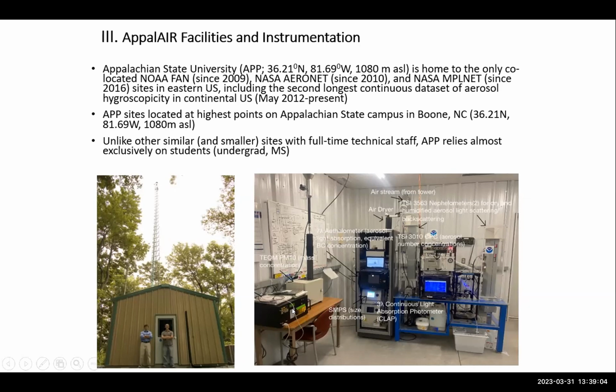This is what's called a tapered element oscillating microbalance, which measures PM10 mass concentrations. This instrument here is called a CLAP. It measures aerosol light absorption. And you have two nephelometers here and here. The first one measures aerosol light scattering and backscattering for dry aerosols. And the second one humidifies them every hour. And from the two, you measure the hygroscopic growth of the aerosols.